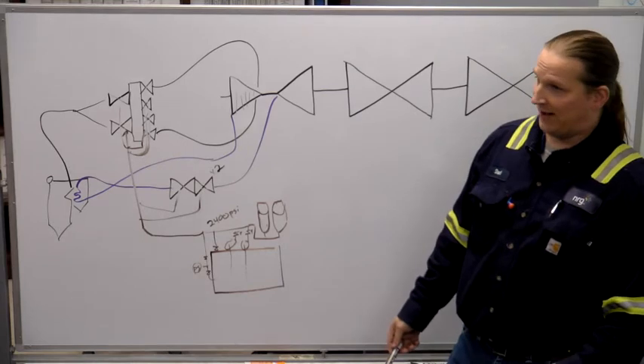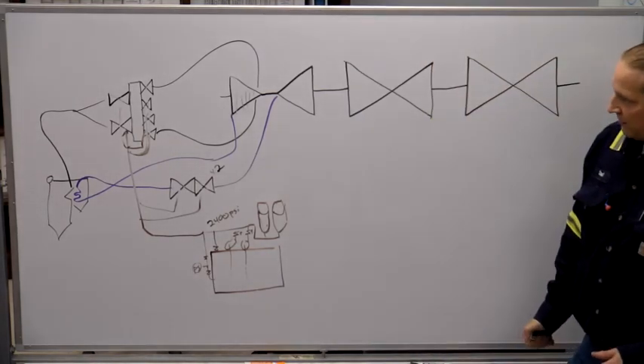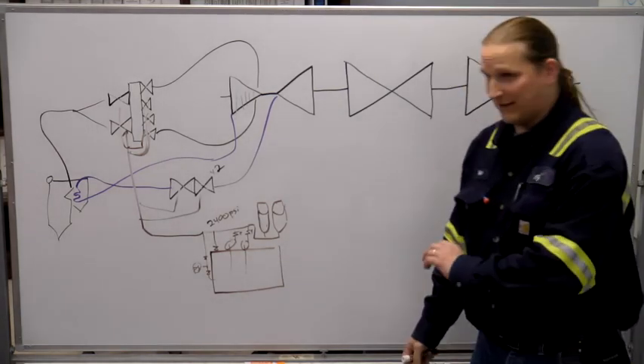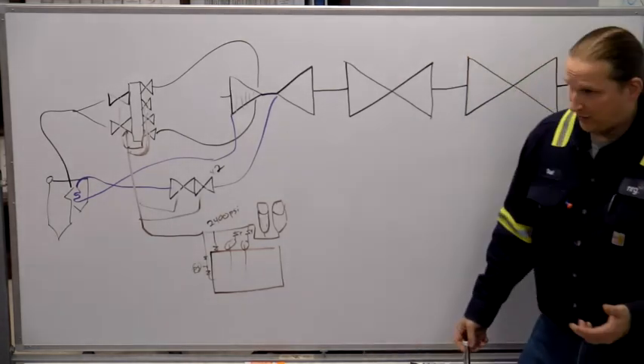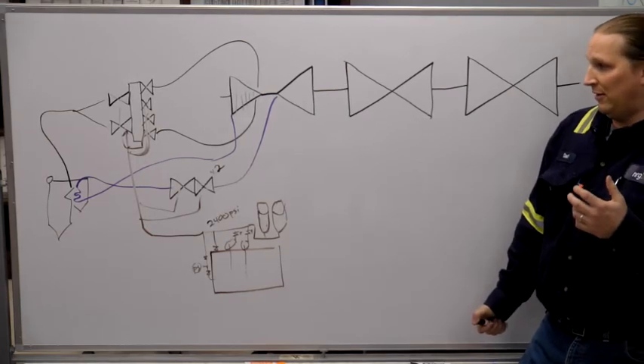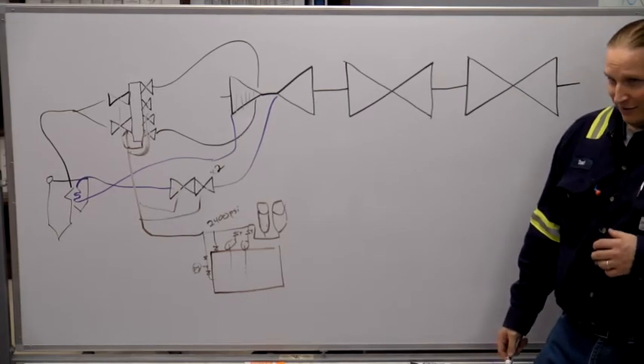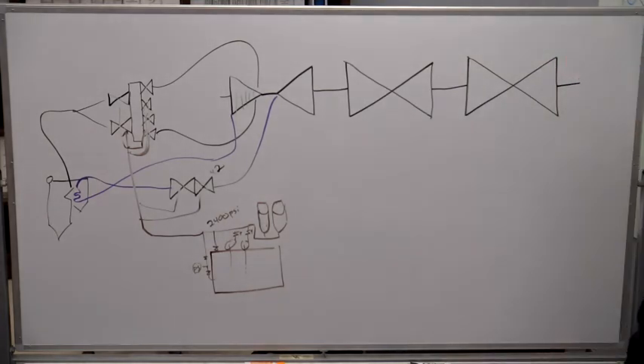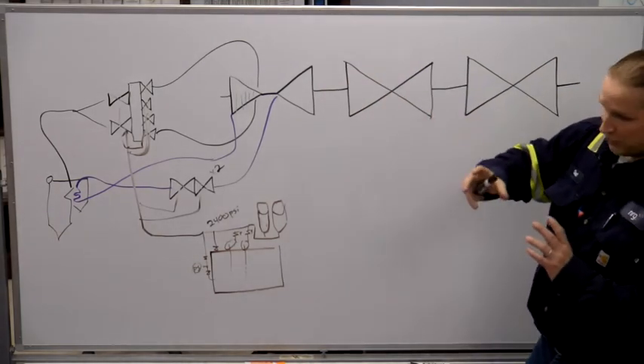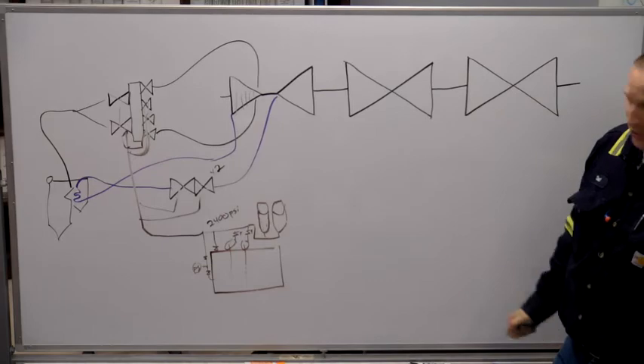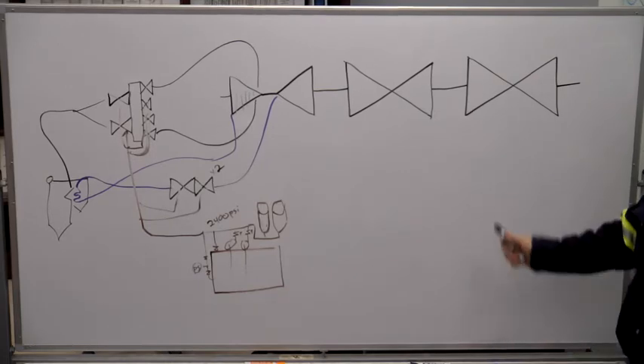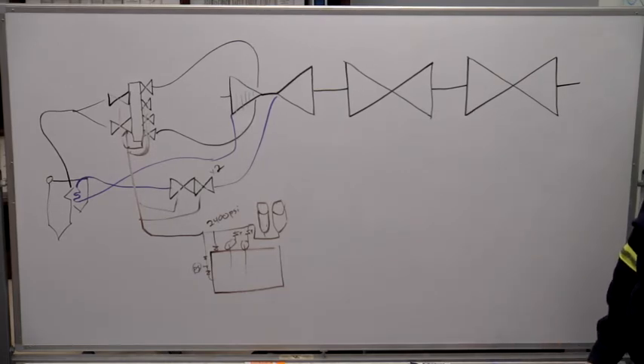Having two trip valves creates an additional chance of a component failing and causing one of these valves to go shut — which isn't quite like tripping, but it would swing the unit around pretty good. It adds reliability in that the worse condition would be a trip valve failing to trip when it was supposed to. Regarding overspeed, the centrifugal force could conceivably swing these larger turbine stages completely apart — throw them all over the place — somewhere around 6,000 RPM.